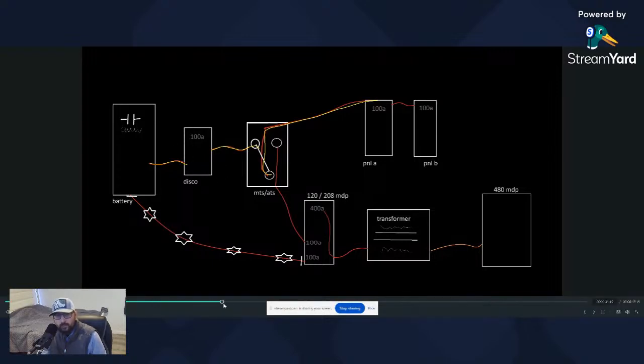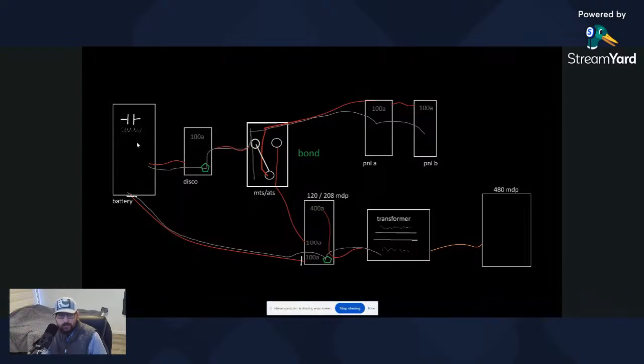One, this battery cabinet did not have overcurrent protection. So much like the transformer, you got to have a fuse or a breaker. This battery cabinet didn't have it from Square D. No fuse, no breaker, nothing, just hot. So we had to have overcurrent protection, but we also needed a place to bond because we got to get all of our current back to the neutral.